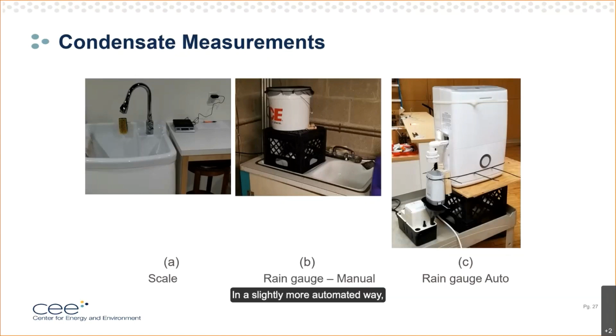In a slightly more automated way, we asked them to dump that bucket through our own bucket, under which we placed a rain gauge that would automatically measure the condensate and forward us that result digitally. Both these methods provided discrete measurements of condensate according to when users emptied their buckets. So they gave us good data about when condensate was collected, but at the consequence of not giving us detailed data about how that condensate was produced over the changes in operating conditions between that moment and the last empty.